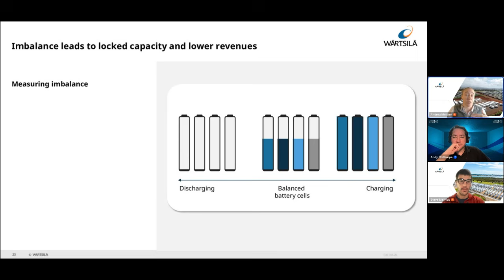This presents a challenge. It could be because of slight differences in battery cell size at manufacturing, how fast it's degraded, or an uneven current draw as the battery discharges and performs other operations. So when we see unbalanced battery cells, that means as the battery discharges, the first cell to hit 0% state of charge stops the whole battery from discharging.